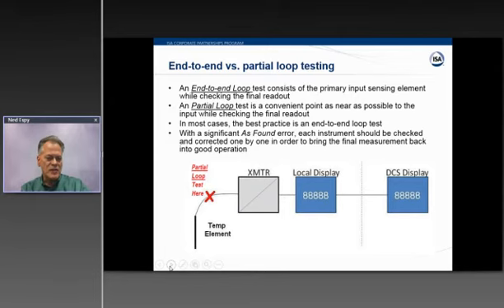If during your testing the loop is out of spec, then you would maybe break the loop down and perhaps the transmitter has drifted. You could make a trim on that and it would bring the total loop back into good operation.